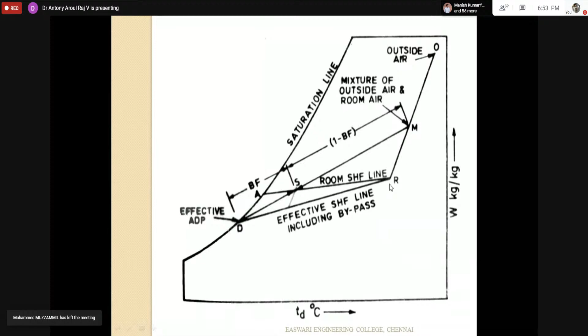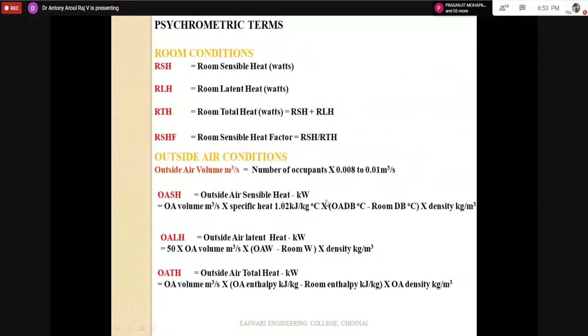So effective room sensible heat is the room sensible heat plus the bypass factor into the outdoor air sensible heat. That is the component we are having, as we just saw. And the air conditioning system heat gain multiplied by the bypass factor. That is very, very important. So here we are taking the room sensible component, and we are also taking the bypass factor component for the outdoor air sensible heat as well as for the system gain. That is what we have to do.